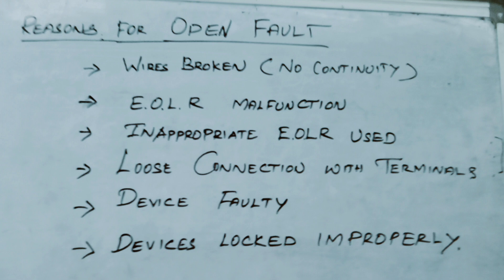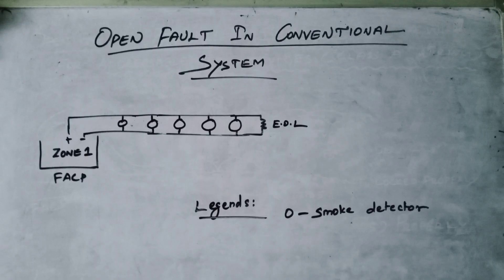Here I'm showing the typical reasons for open trouble: broken wires, faulty end-of-line resistor, inappropriate end-of-line resistor used, loose wiring terminations, faulty devices, or devices locked improperly.